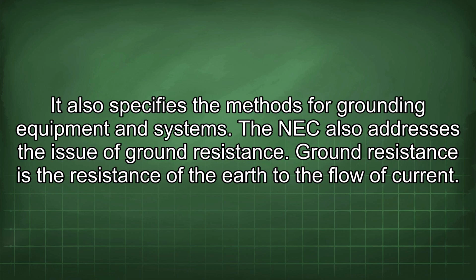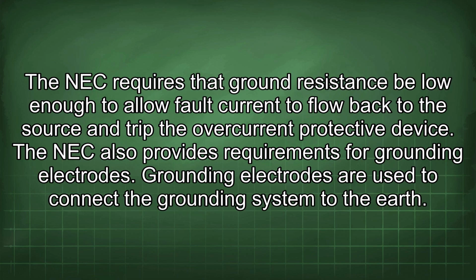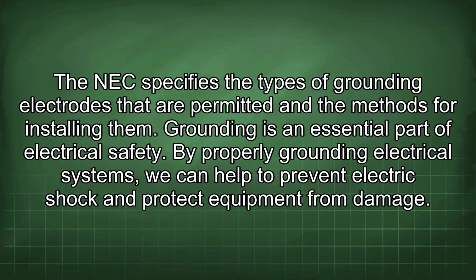The NEC also addresses the issue of ground resistance. Ground resistance is the resistance of the earth to the flow of current. The NEC requires that ground resistance be low enough to allow fault current to flow back to the source and trip the overcurrent protective device. The NEC also provides requirements for grounding electrodes. Grounding electrodes are used to connect the grounding system to the earth. The NEC specifies the types of grounding electrodes that are permitted and the methods for installing them.